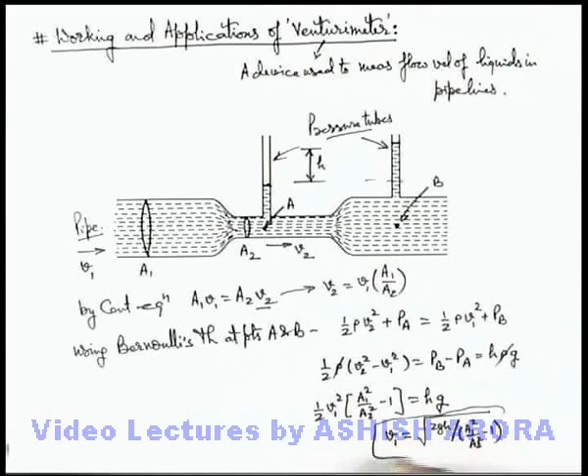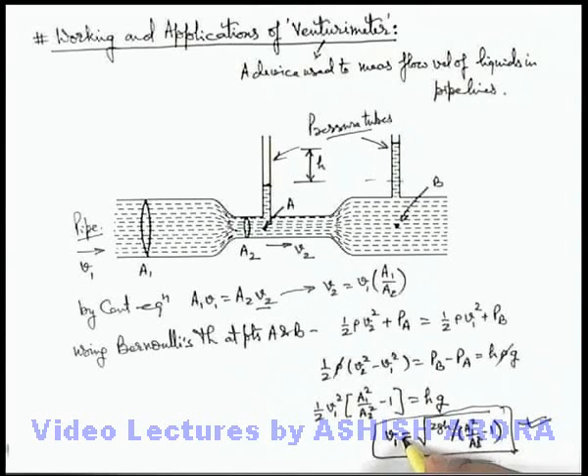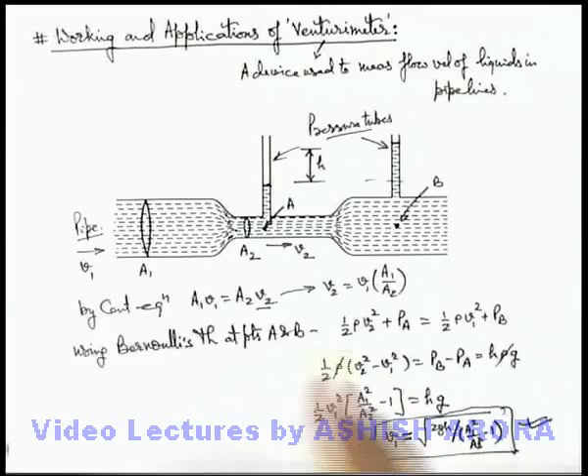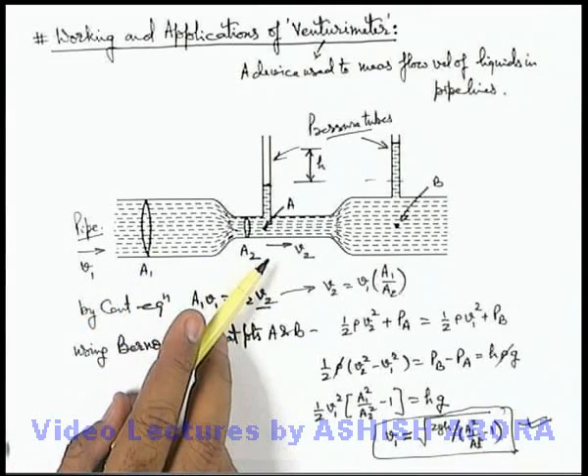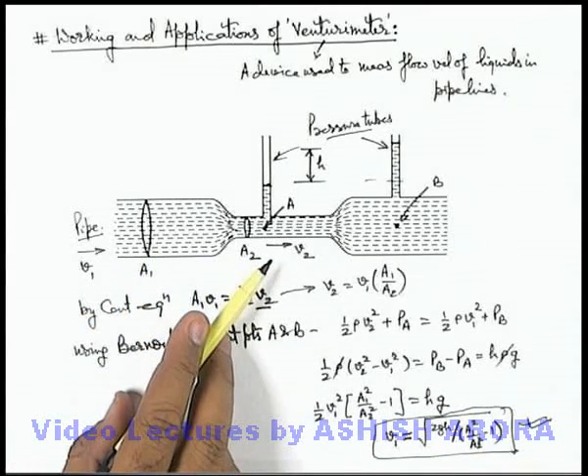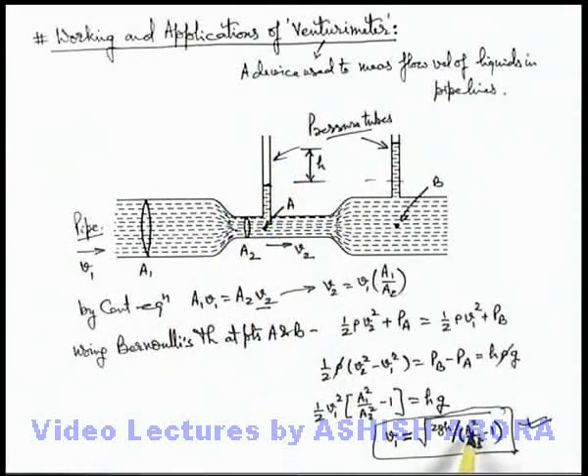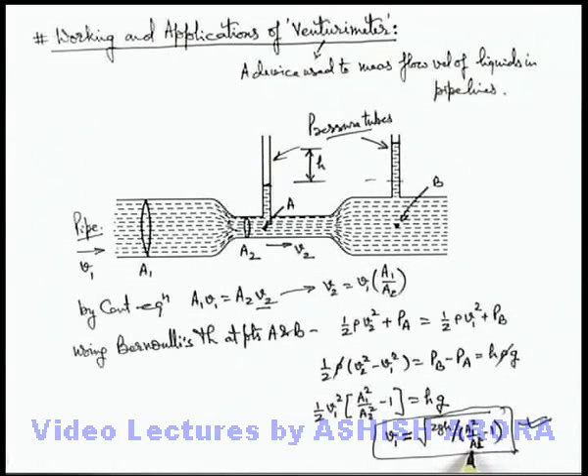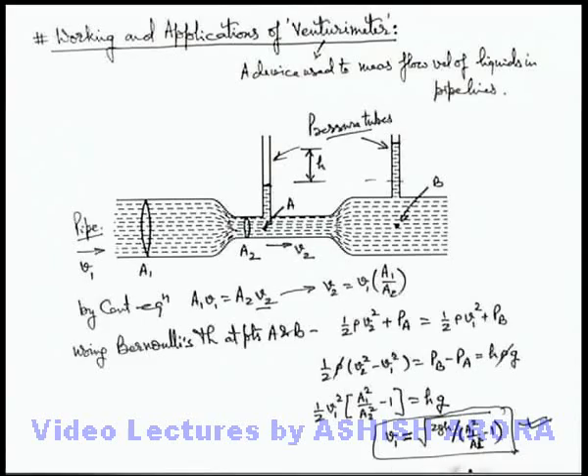This is quite a useful expression you should always keep in mind which is giving us directly the flow velocity of liquid in pipelines through which a venturimeter is connected. The only thing which we need to measure is the difference in liquid level in the two pressure tubes as well as the cross sectional area of pipe and that of constriction. This is giving us the result of flow velocity of liquid.